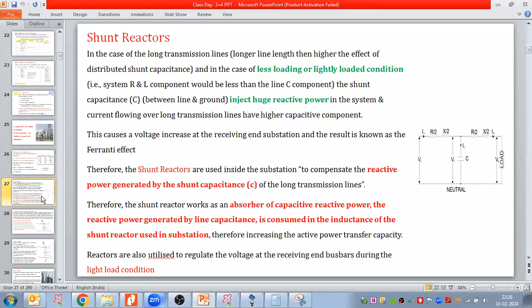So let us model a transmission line using ETAP. Here we are taking a 350 kilometer long line connected from the sending substation to the receiving substation. Let us assume no load is connected to the receiving end substation. But after doing the load flow analysis, the below result came. 2.16 megawatt of real active power is flowing from the sending substation to the receiving substation, so it is real power loss. And the minus 199.9 MVAR is power generated by the transmission line and injected into the grid system. Therefore, it appears with a negative sign, and this is the power injected by the capacitance of the line.